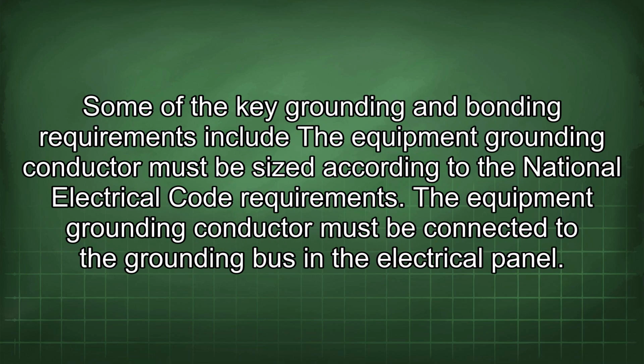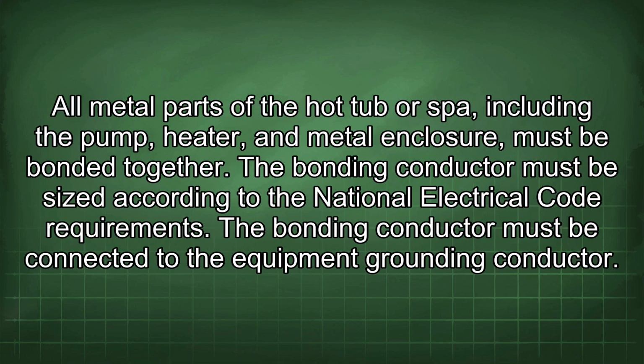shock. Some of the key grounding and bonding requirements include the equipment grounding conductor must be sized according to the National Electrical Code requirements. The equipment grounding conductor must be connected to the grounding bus in the electrical panel. All metal parts of the hot tub or spa, including the pump, heater, and metal enclosure, must be bonded together. The bonding conductor must be sized according to the National Electrical Code requirements. The bonding conductor must be connected to the equipment grounding conductor.